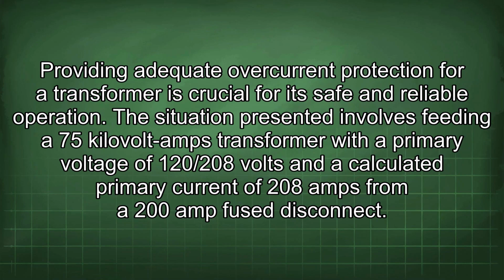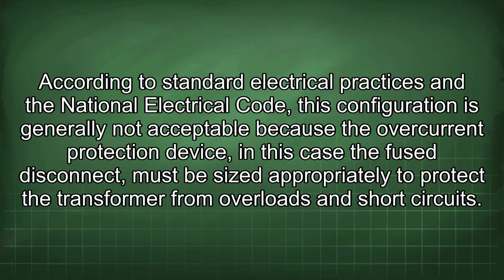Providing adequate overcurrent protection for a transformer is crucial for its safe and reliable operation. The situation presented involves feeding a 75 kVA transformer with a primary voltage of 120/208 volts and a calculated primary current of 208 amps from a 200 amp fused disconnect.